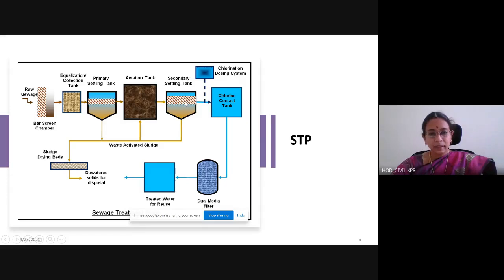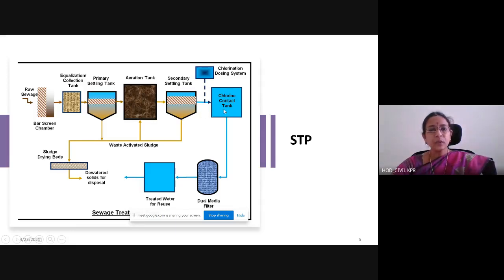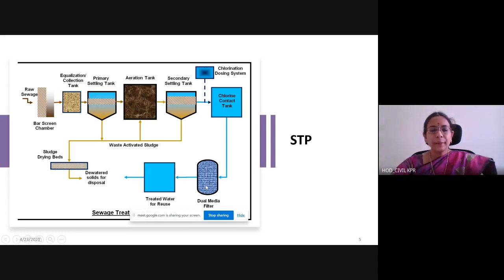After the secondary settling tank comes the contact tank, which is the disinfection tank. In most cases, chlorination dosing is being done — chlorine is the main parameter used for disinfection. After disinfection, the effluent is taken to a filter media. The filter media might have a single media or a dual media, or two different filters can be placed in a separate treatment plant. The media may be gravel, sand particles, or activated carbon — any type of media can be used for filtration.